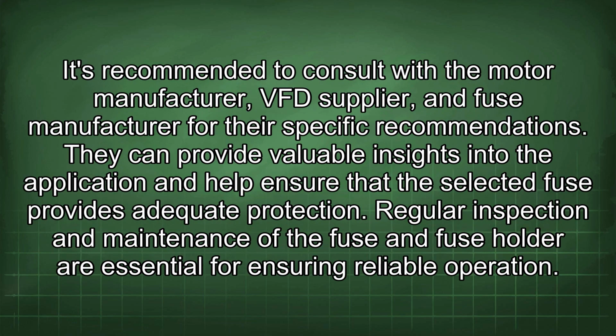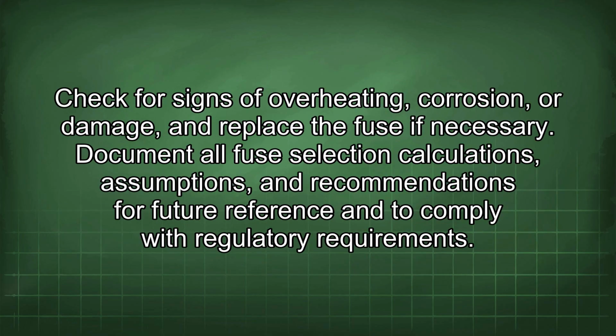It's recommended to consult with the motor manufacturer, VFD supplier, and fuse manufacturer for the specific recommendations. They can provide valuable insights into the application and help ensure that the selected fuse provides adequate protection. Regular inspection and maintenance of the fuse and fuse holder are essential for ensuring reliable operation. Check for signs of overheating, corrosion, or damage and replace the fuse if necessary. Document all fuse selection calculations, assumptions, and recommendations for future reference and to comply with regulatory requirements.